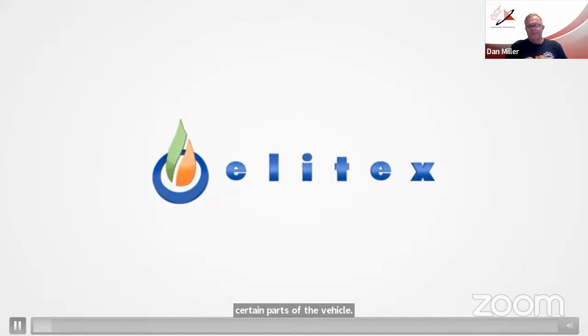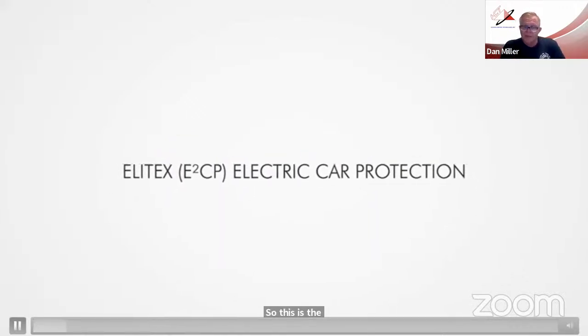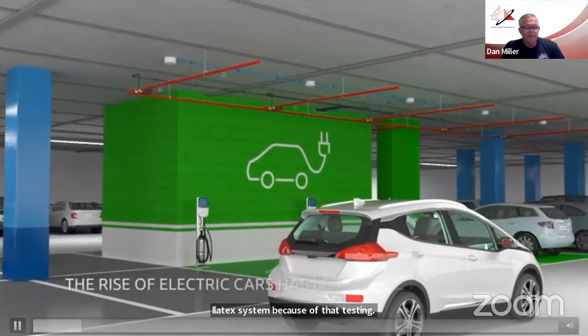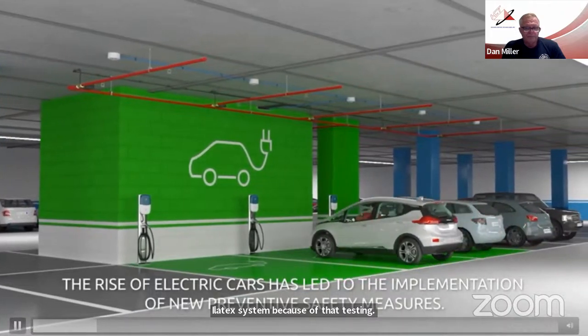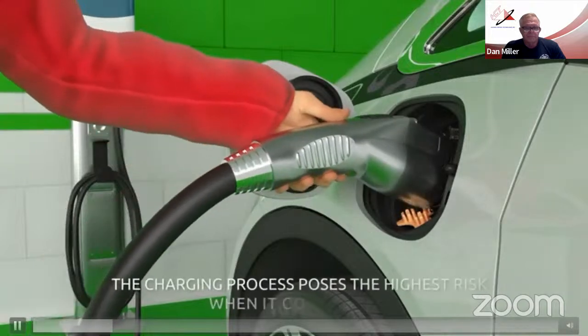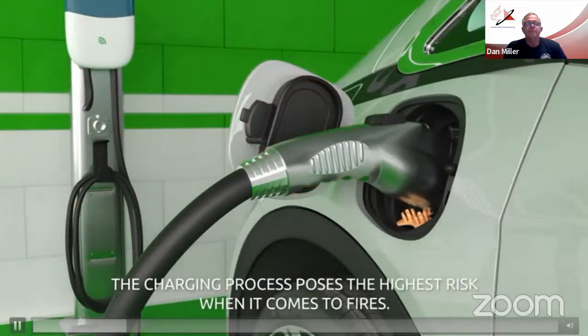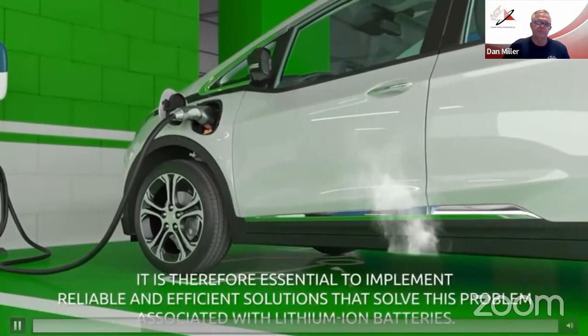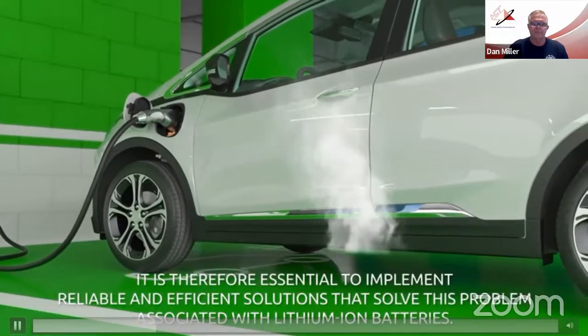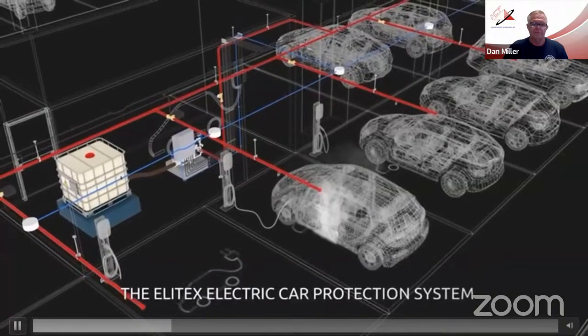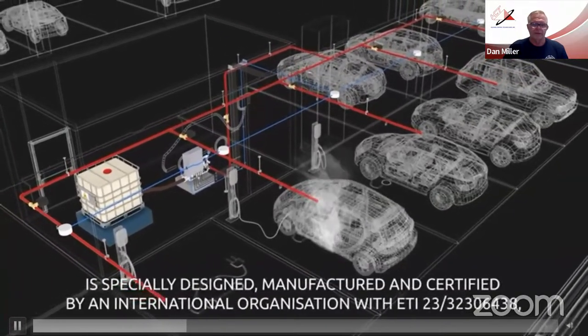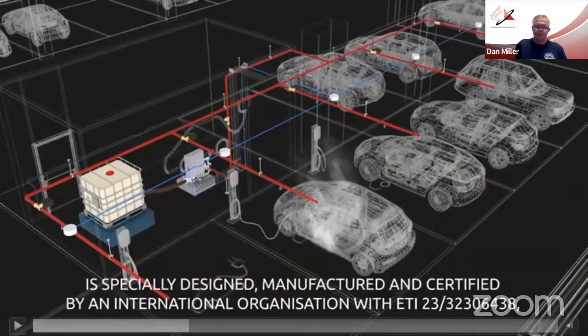So this is the commercially available Elitex system because of that testing. I'm going to pause it here. You have triple mode detection here. So you have photo detection, you have rate of rise detection, as well as smoke detection. So we're catching it a few different ways. And then as you'll notice, it is a deluge, not a closed head sprinkler system.